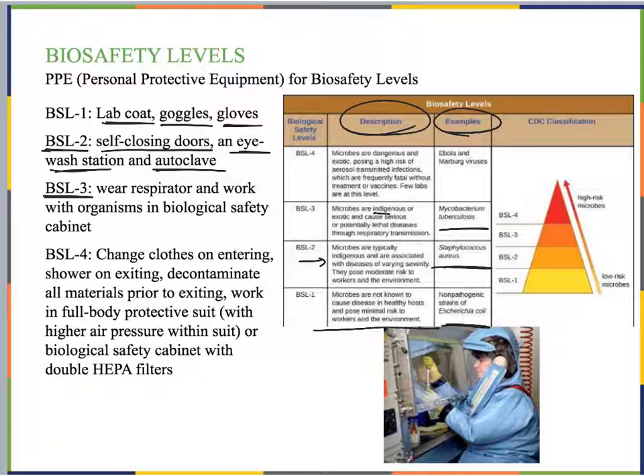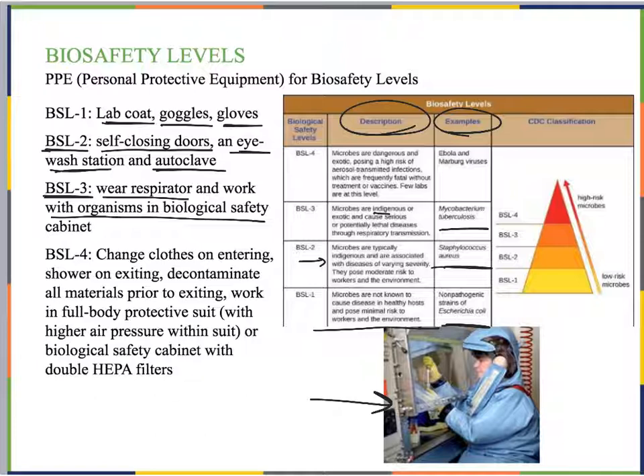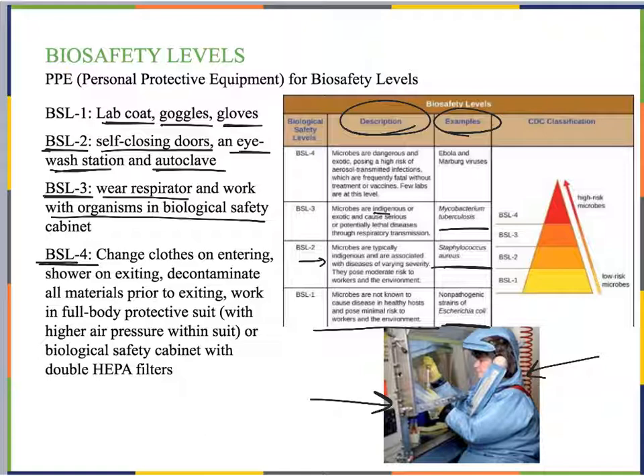In BSL-3 laboratories, people need to use a respirator when working because infection could be through respiratory transmission and could be lethal. They also work with organisms in a biological safety cabinet — similar to a fume hood — where organisms are manipulated within the cabinet. It has airflow pulling anything away from the room and person, and filters ensure nothing escapes into other spaces.